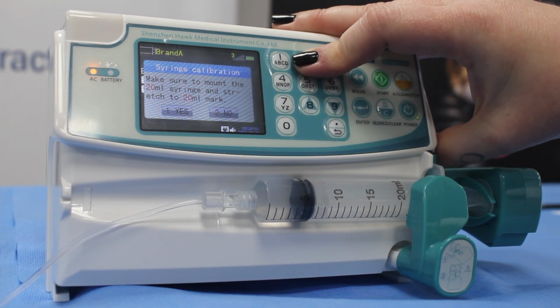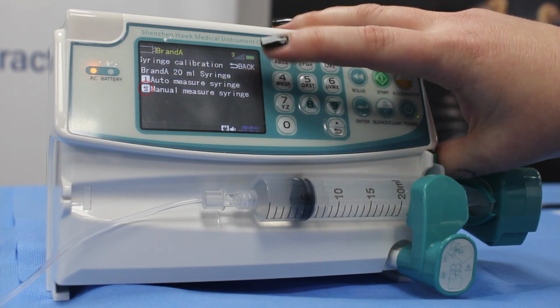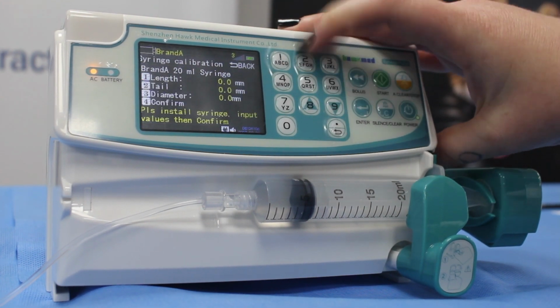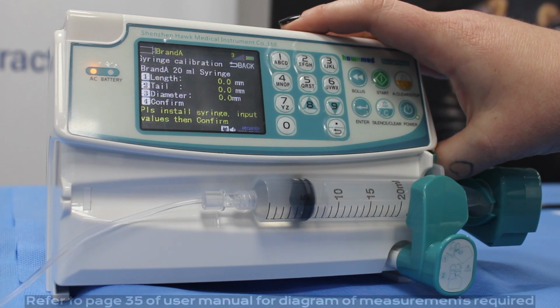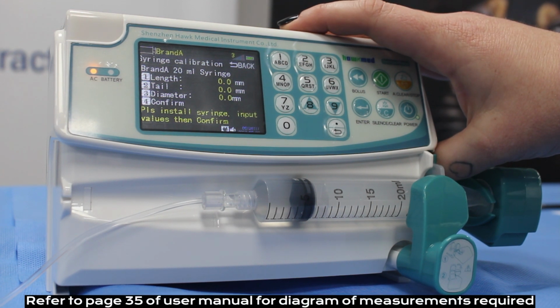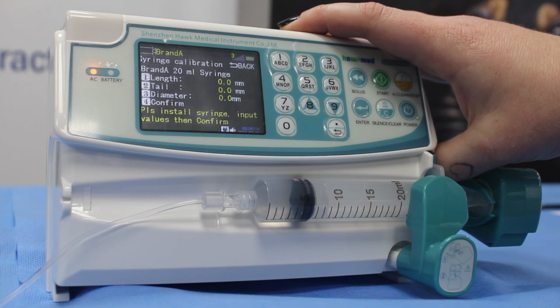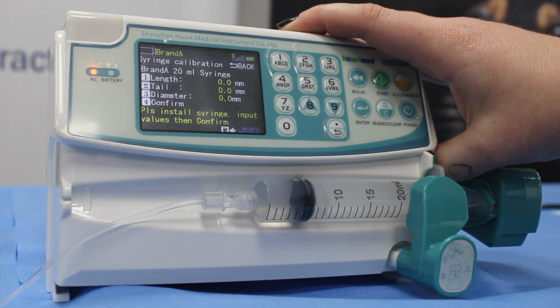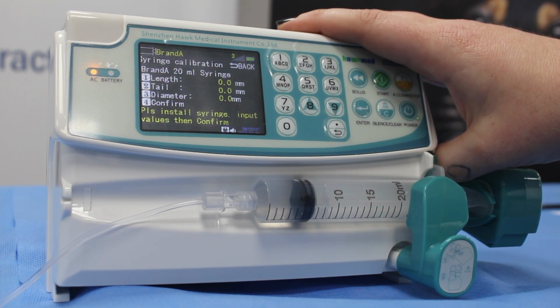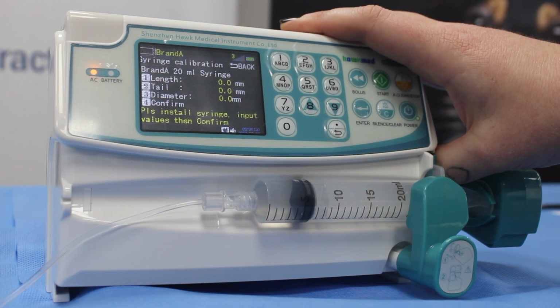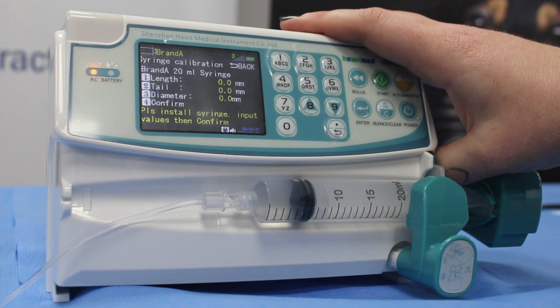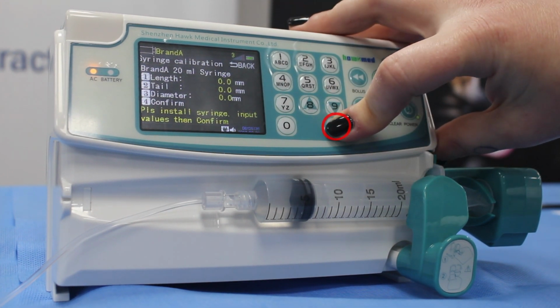We'll go back with no at this stage, number 2, and we will have a look in the manual measurement of syringe, which is number 2. Here you would manually measure and enter your length, tail and diameter of your syringe, and then press 4 to confirm. Before pressing confirm, we would install the syringe so that the syringe pump can calibrate and recognize the different lengths you've entered so that it can enter these for the brand selected. We can go back with our back arrow.